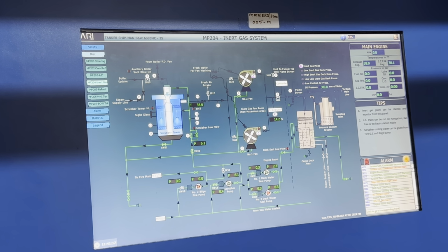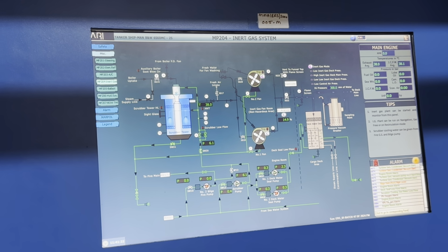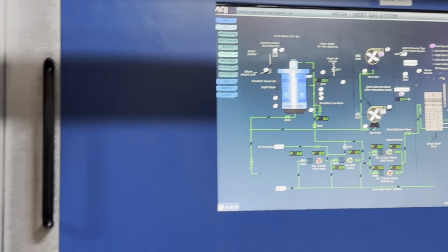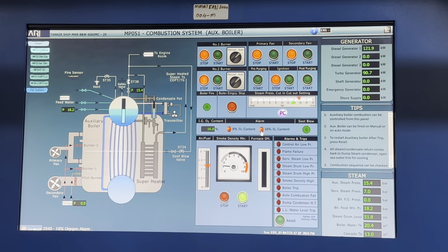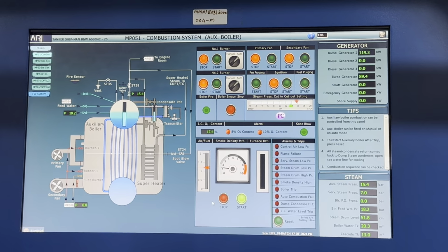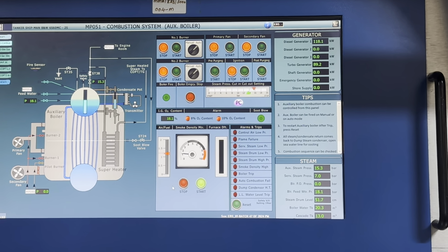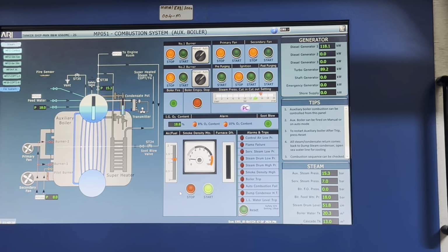So now less than 5. For doing that, what do we do? I mean, how do we do the less than 5? We can adjust the O2 content. We can come here and see for the boiler combustion. Say this is what the 8-10% came, the alarm came. So what we can do, the minimum air required for combustion, what is that air ratio known as? Stoichiometric air ratio. Very good.